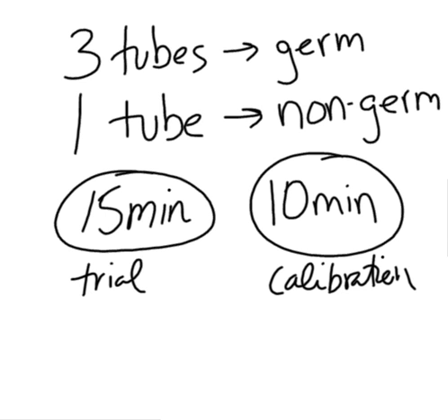Okay. There's no reason why you can't do more than 1 tube at one time. In fact, I encourage that. If you do, say, 2 at a time, then that will allow you to, while you're calibrating one, be setting up the other one, and then once the calibration for the first set is done, you can start the second set, and then while that second set is run, of course you'll have the next one calibrated and ready to go.